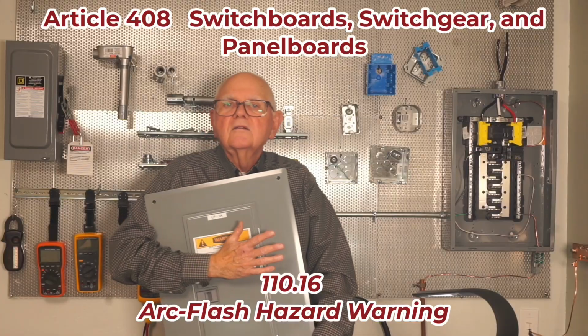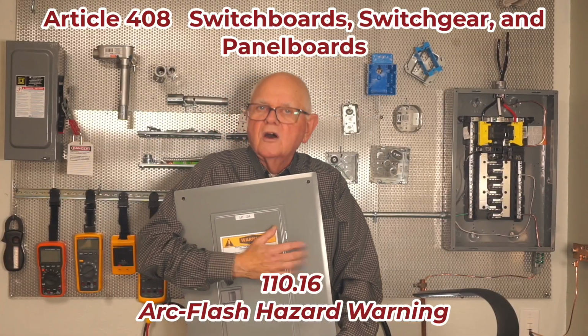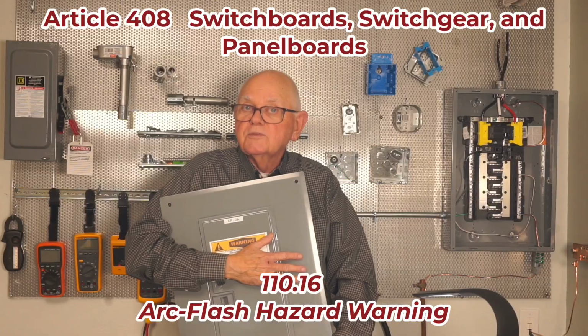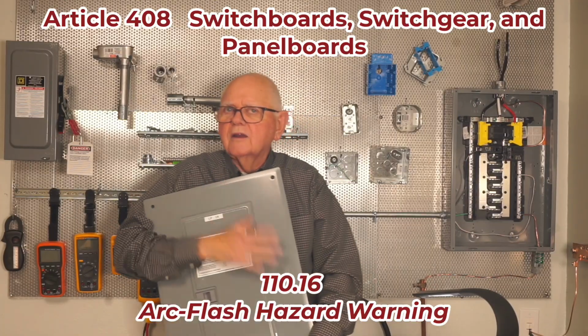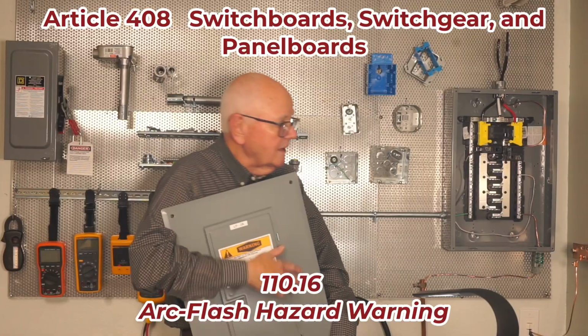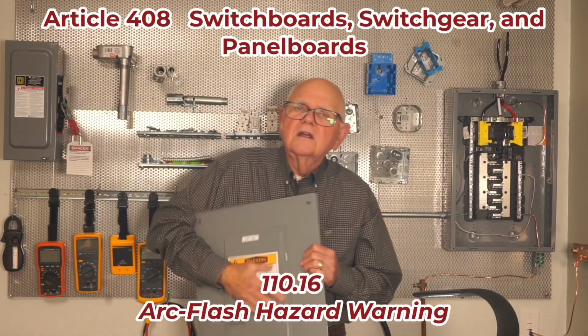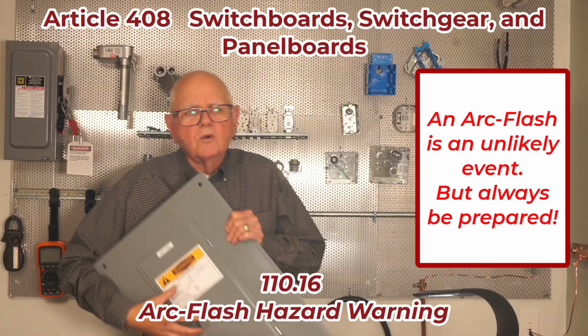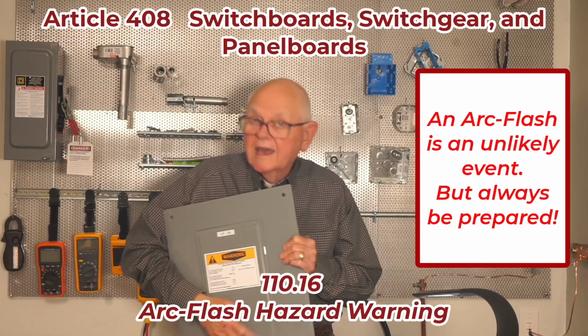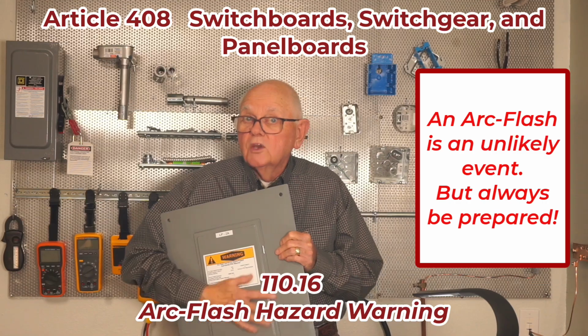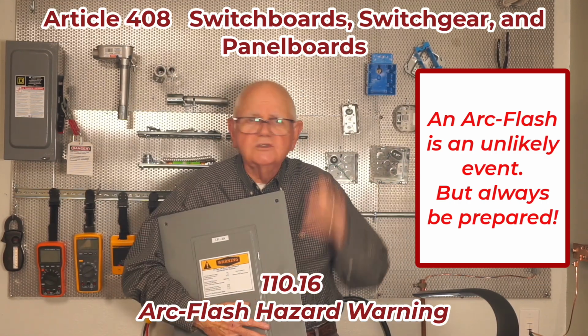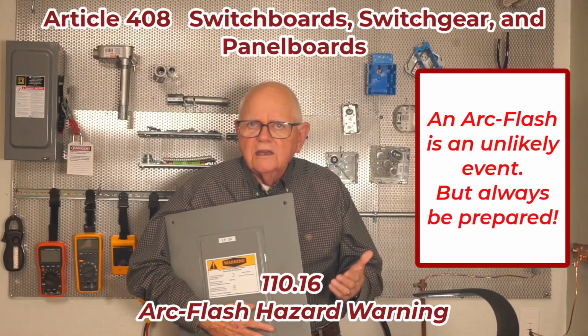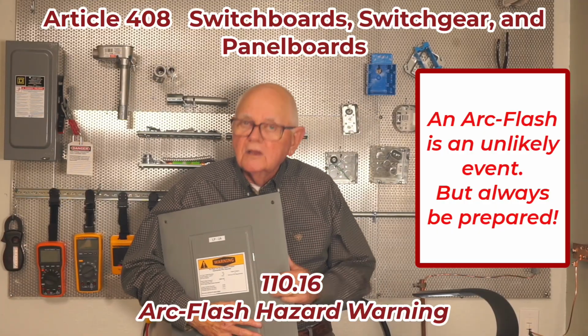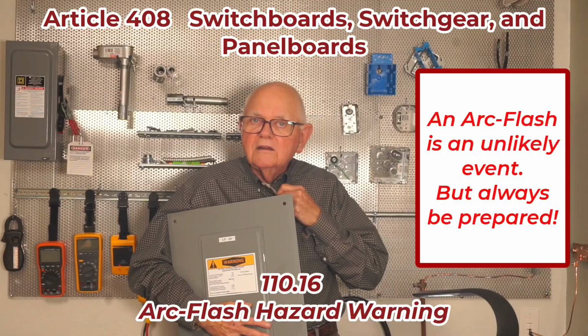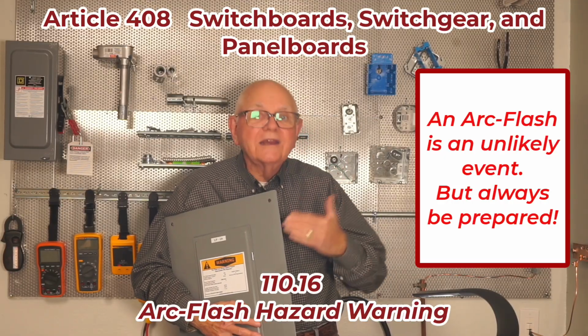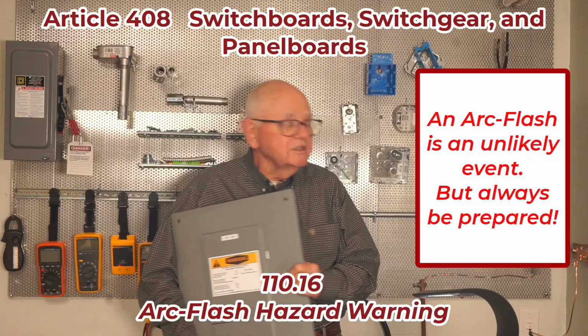So we need that voltage rating, the nominal system voltage, on our label so we know what type of voltage protection we need. It'll also play into the barriers and maybe the barricades that we have to set up. The other bit of information that we're going to need on the front of the panelboard, on that arc flash warning label, is the actual arc flash information itself. In the unlikely event, they don't give it to us in degrees Fahrenheit or anything like that, they give it to us in calories per square centimeter. We have to make sure that the clothing that we wear is rated for at least that rating or above, whatever that arc flash energy is that's going to come out of there.